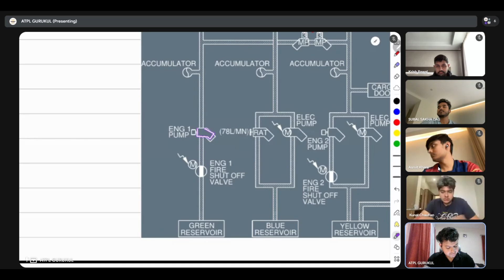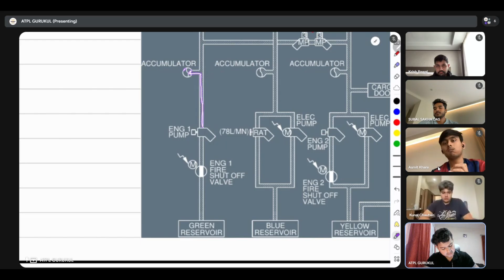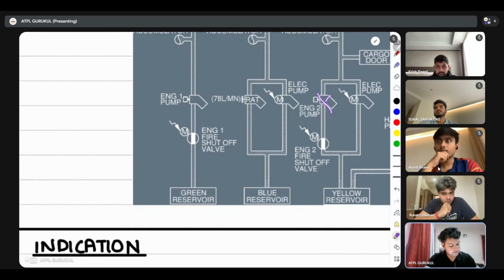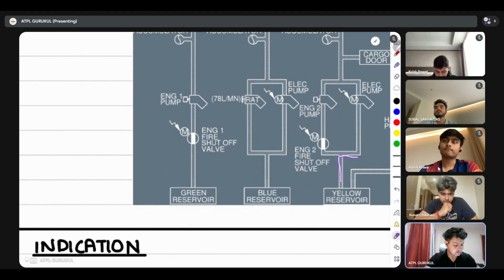What is an accumulator? Accumulator is a place where you can store fluid under pressure. Okay, so the fluid goes over here, and it is stored against the pressure over gas, and thereafter goes through its systems. And the same चीज यहाँ पर भी है. When it goes through the yellow reservoir से भी आपके पास दो चीजें parallel में चल रही हैं. पहली वाली है engine 2 fire shut off valve through the engine 2 pump, which is the same line as this. However, if the engine number 2 is not running, the engine 2 pump will not run, then fluid can be supplied via the yellow electric pump as well.